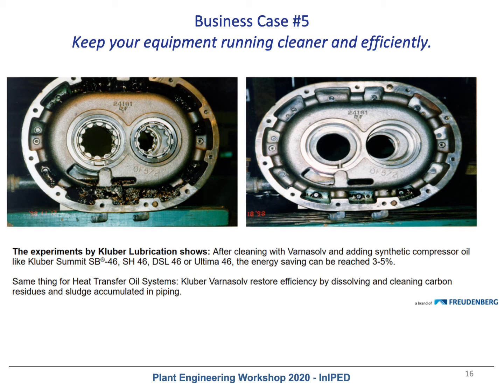more output. That means that most of the new and modern equipment used by chemical companies is running faster, at a warmer temperature, and also has less oil in the oil sump. The oil is now exposed to extreme and continuous service and also extreme temperature. And if mineral oil is used in an application like a modern compressor, it could break down quite rapidly and degrade by generating varnish, sludge, or carbon buildup in this equipment. It's really important to keep your equipment clean. That will really influence the global efficiency of the equipment.